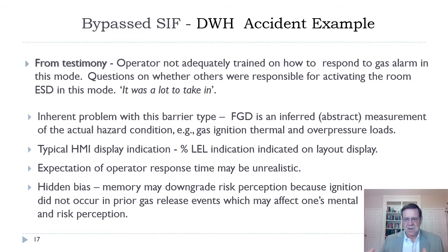In the design of a facility, I have a gas cloud of a certain size in a certain place, and on ignition those thermal loads and overpressure loads are the basis for design. The question is, does the operator know that? Does percent LEL actually make sense cognitively? And when you look at the response time, was that realistic?